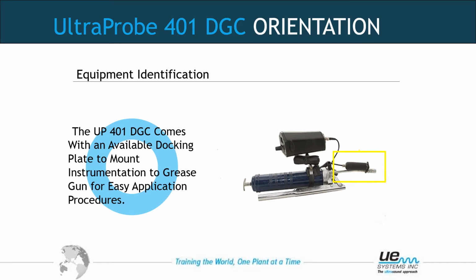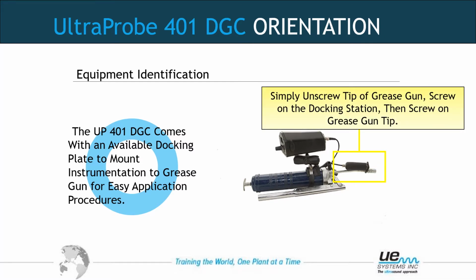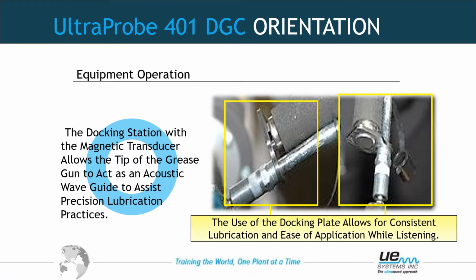The Ultraprobe 401 digital grease caddy comes with an available docking plate to mount instrumentation to the grease gun for an easy application. Here we see the docking plate attached to the actual grease gun, and it gives the magnet a place to rest. Simply unscrew the tip of the grease gun, then screw on the docking station and the grease gun tip. Here we have some close-up photos of the actual docking plate for the magnetic transducer. The sound wave will travel up the grease fitting onto the nozzle of the grease gun and to the docking plate, all metal-to-metal contact, which is good sound transfer.